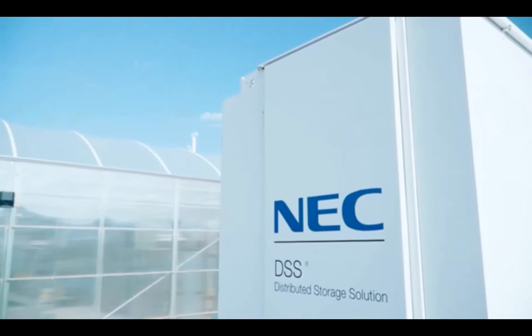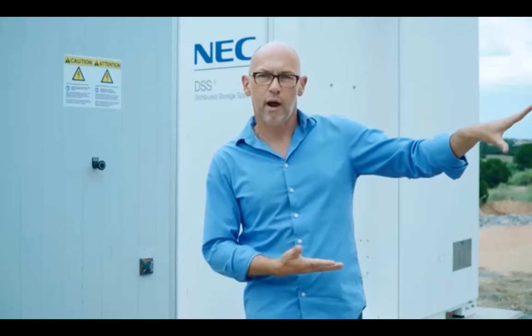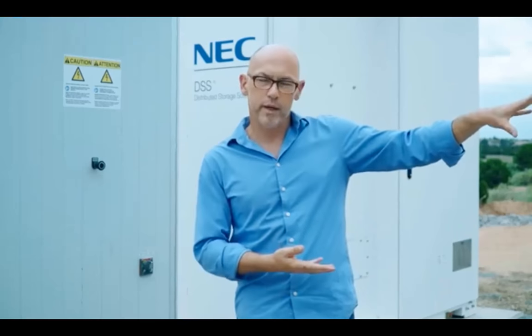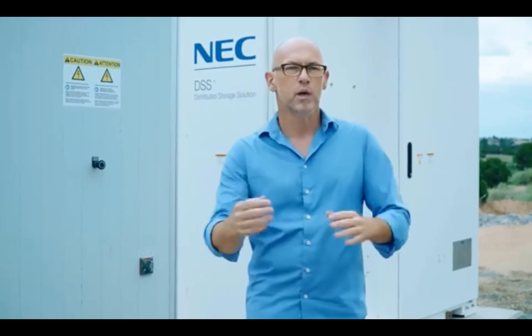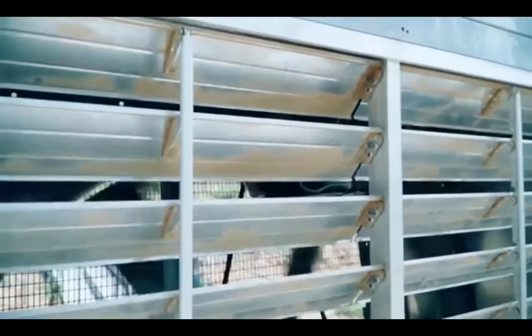The 85 kilowatt hours is able to serve our nanogrid, our greenhouse, which is about a 10 kilowatt load right now. So depending on the mode of operation and what we need to do, it can serve its peak load for probably less than 8 hours, 6 to 8 hours.